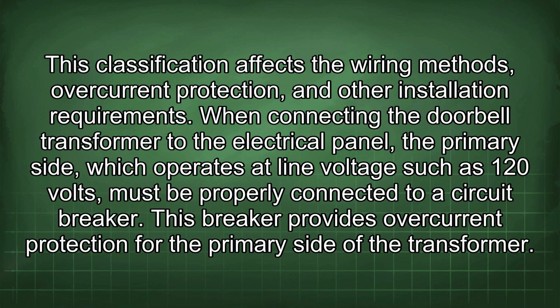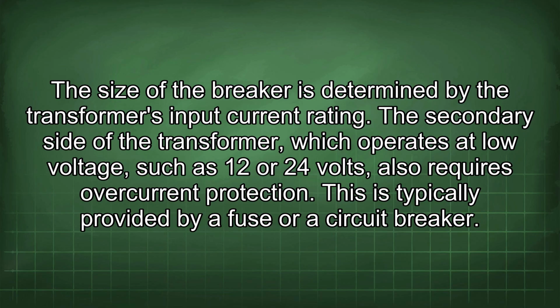When connecting the doorbell transformer to the electrical panel, the primary side, which operates at line voltage such as 120 volts, must be properly connected to a circuit breaker. This breaker provides overcurrent protection for the primary side of the transformer. The size of the breaker is determined by the transformer's input current rating.